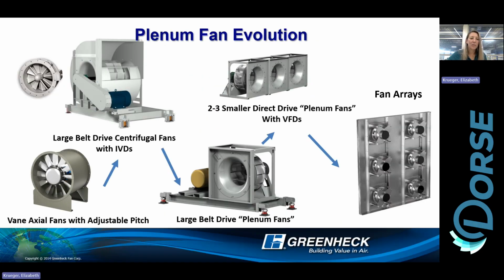But I will jump right into our fan evolution here. So, plenum fans, and I'll show you a few pictures of these applications. I'm not going to leave you hanging if you don't know what a plenum is or you haven't seen one. Basically, we're talking about air handling units. We're talking about rooms, sometimes just a plenum room, where they had a big fan, or some of these straight vane axial fans in there. They went from vane axial to these big double wide. Again, these are in the basement in boiler rooms.